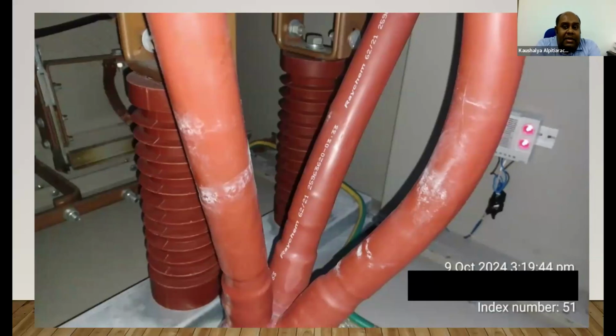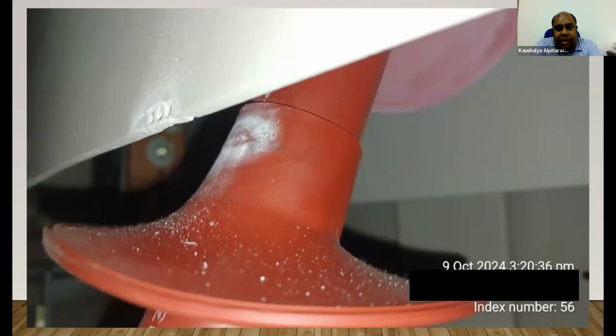You will see some dust deposits, and maybe the insulation cleaning and stress tube installation of the particular medium voltage termination kit might not have been done in a proper way. So the partial discharge is developing and will prematurely fail the cable system. This is another example of partial discharges and voltage tracking.